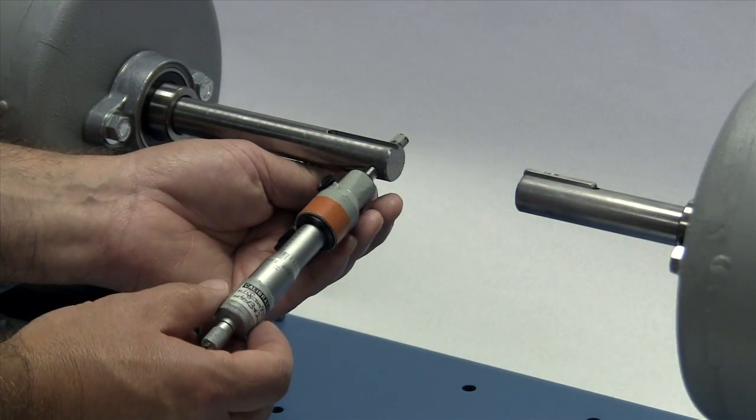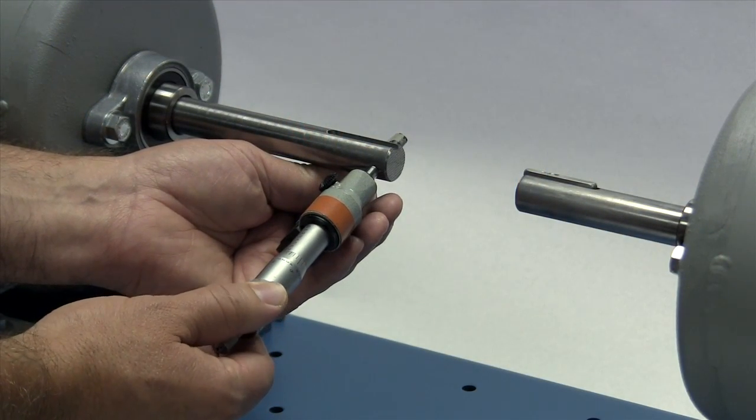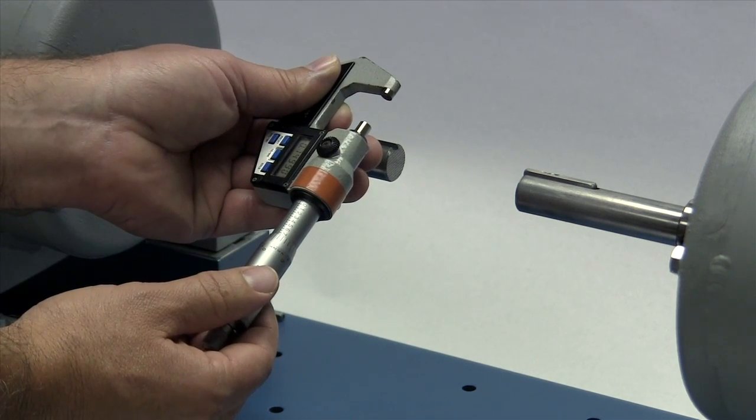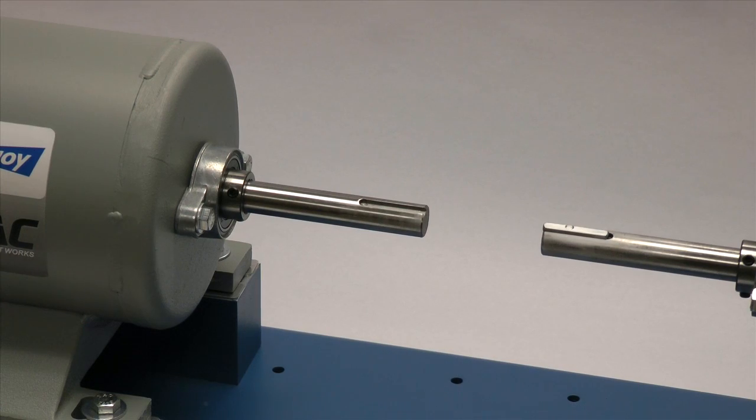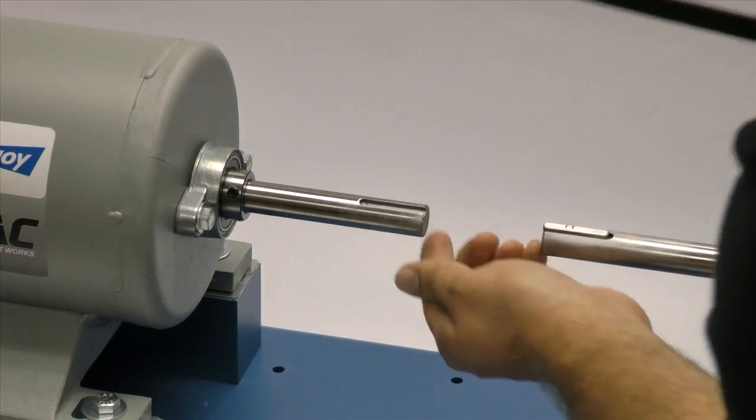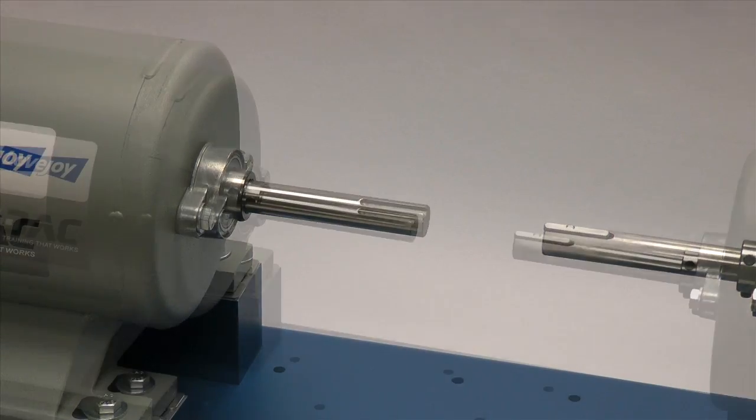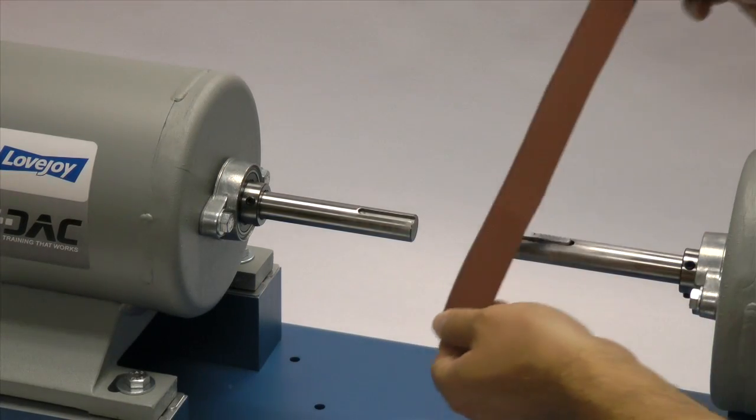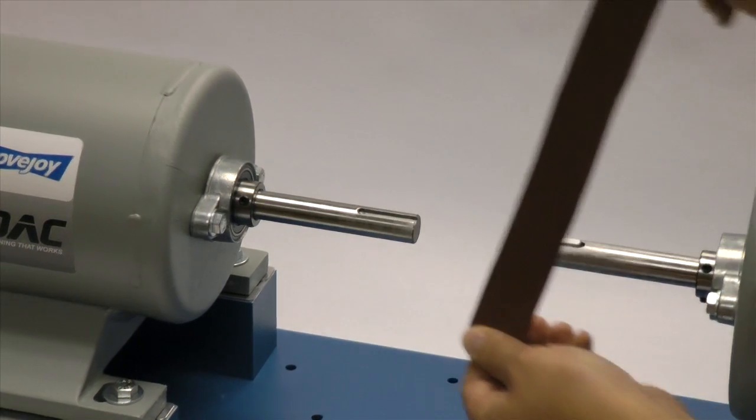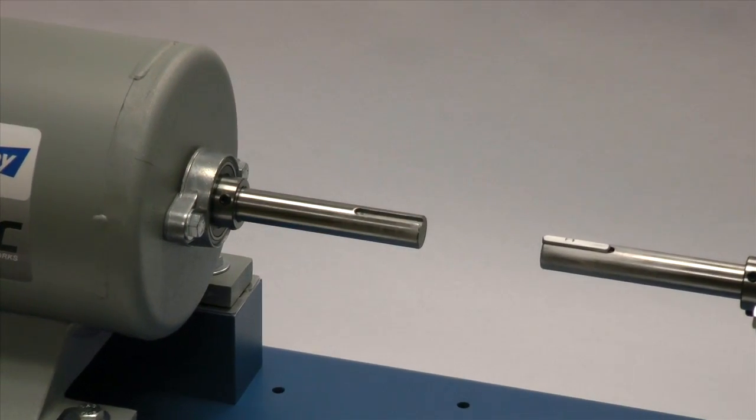If not done already, you should measure the shaft and ensure that the shaft diameter matches the coupling bore size. Then inspect the shaft and clean up any nicks or burrs from the keyway or shaft diameter. A fine tooth file can be used to clean burrs from the edge of the keyway or large dents in the shaft. The emery paper can be used to clear the shaft of rust or any fretting corrosion.